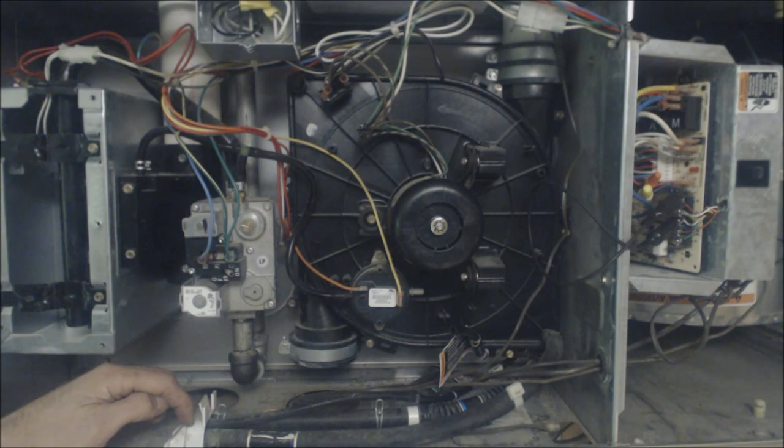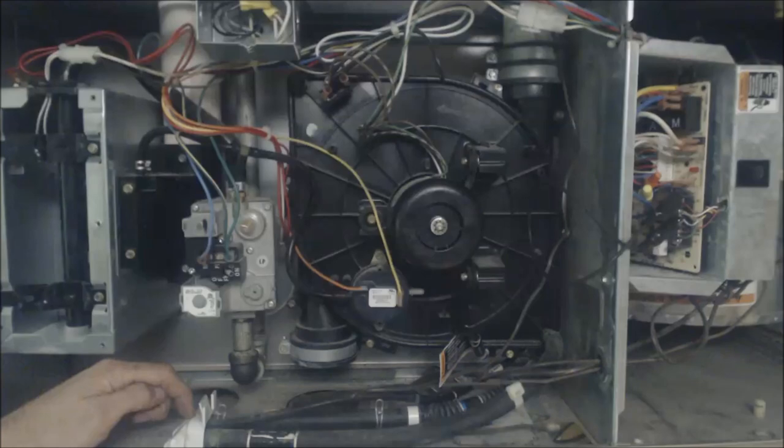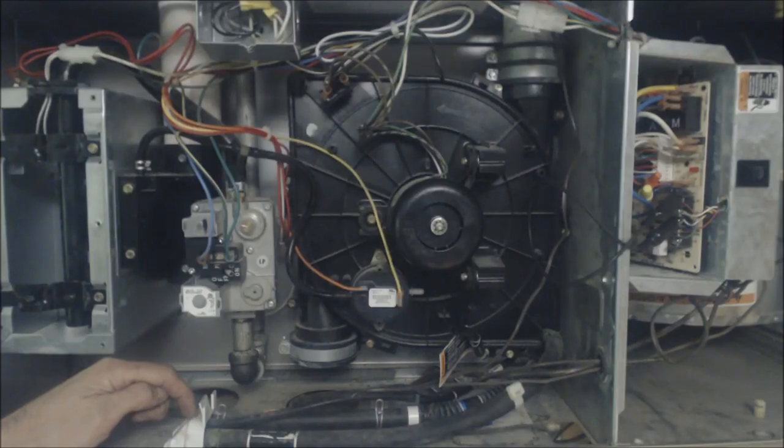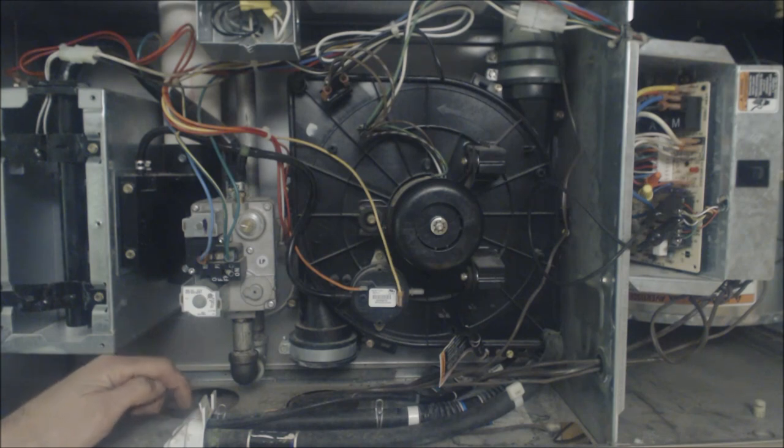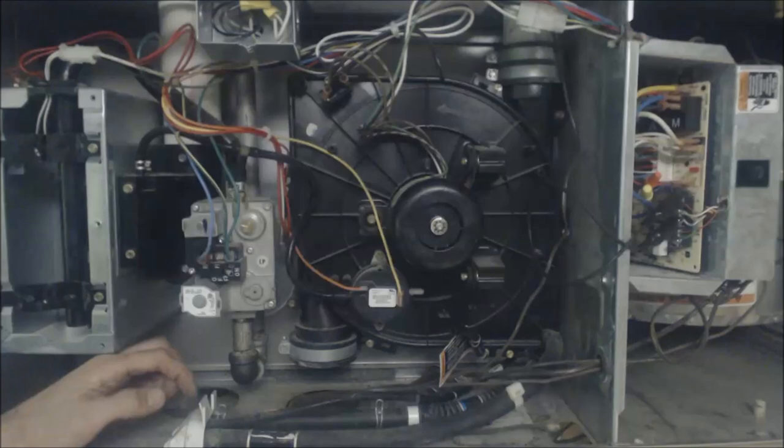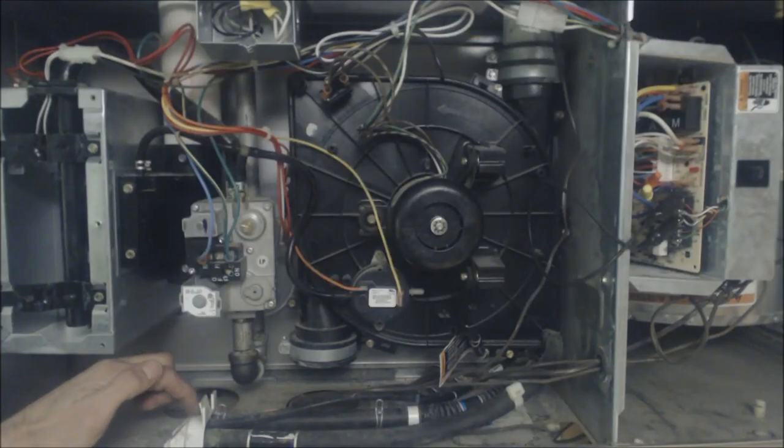But we normally in the field are typically going at least a quarter inch of pitch per foot downwards or more, but an eighth of an inch is normally the codes that we're following. But we typically pitch it much more than that because you don't want water sitting in the condensate pipe.